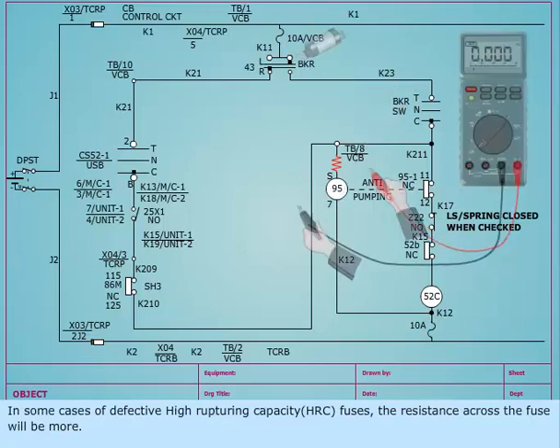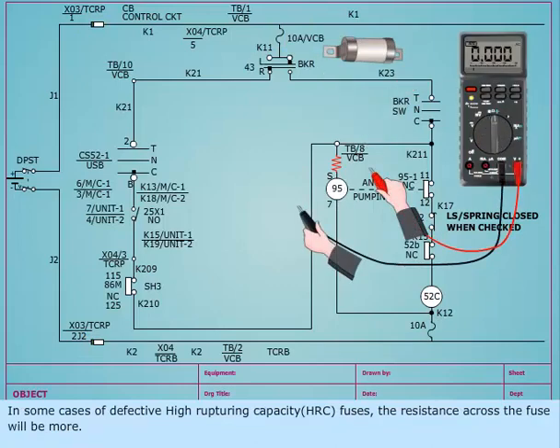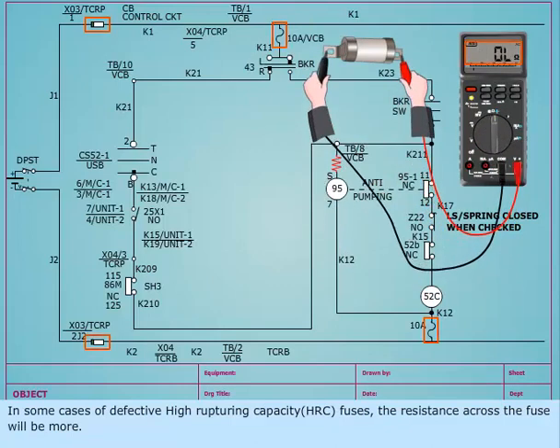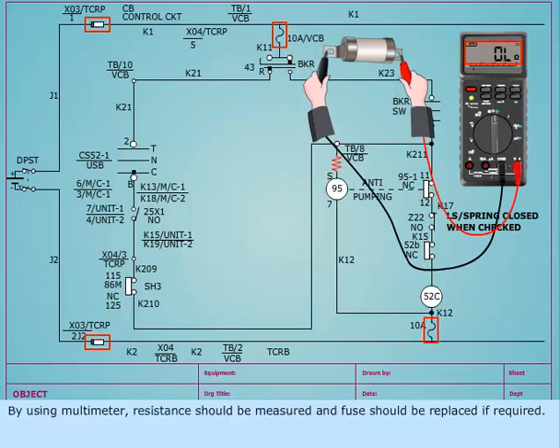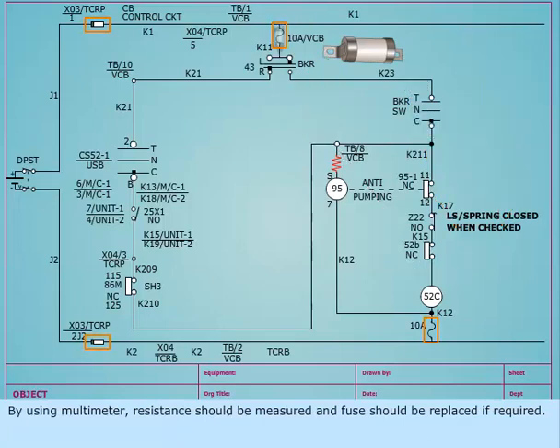In some cases of defective high rupturing capacity HRC fuses, the resistance across the fuse will be more. By using a multimeter, resistance should be measured and the fuse should be replaced if required.